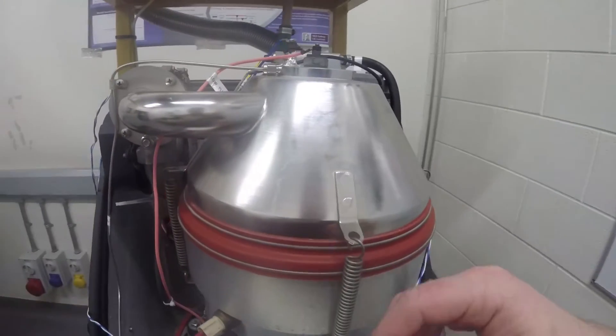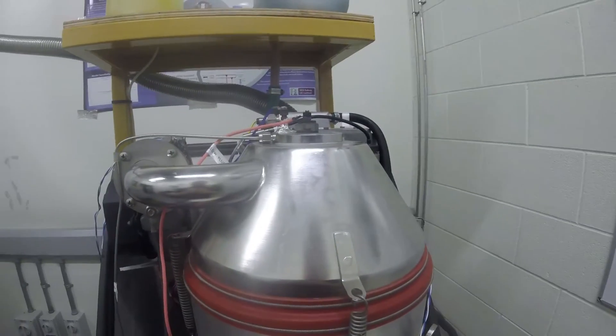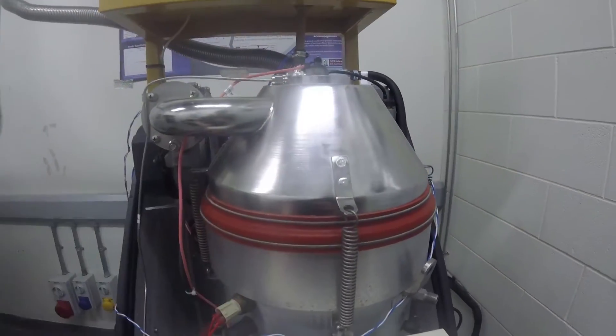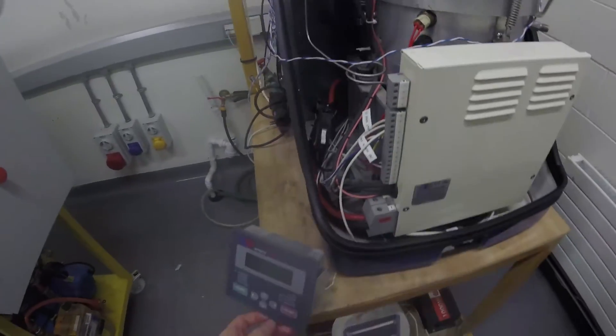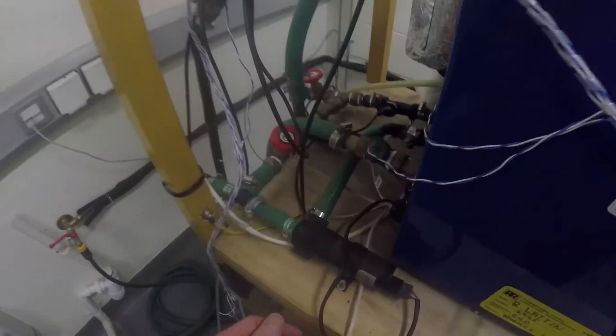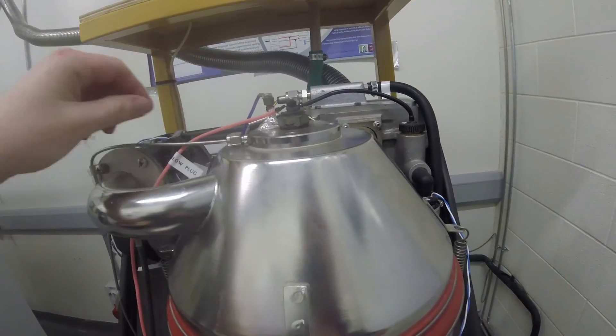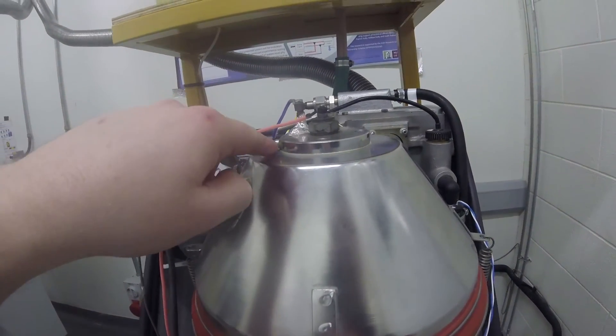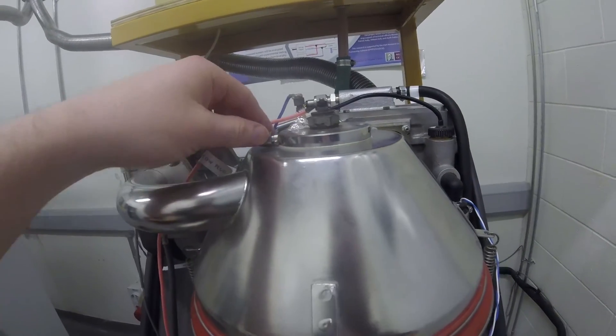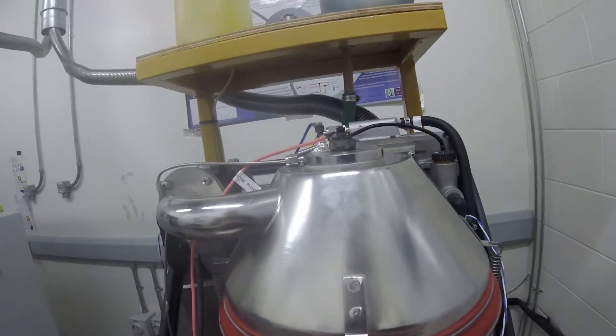Some other important parts are the diesel fuel line here. If for some reason the system runs dry, you will need to turn on the engine at the controller, go into one of the diagnostic menus, into the fuel bleed. That will activate the fuel pump, which is this small little pump down here. It will make a clicking noise and it may be necessary to get a spanner up here and loosen this. You'll let the engine keep running, keep pumping fuel until you get small droplets of fuel coming out up here. Once you've done that, you can be sure that you've purged the airlocks and you reseal the fuel line again.